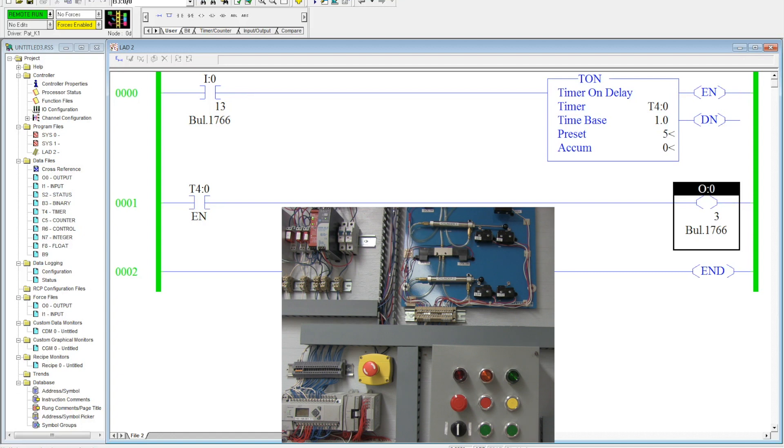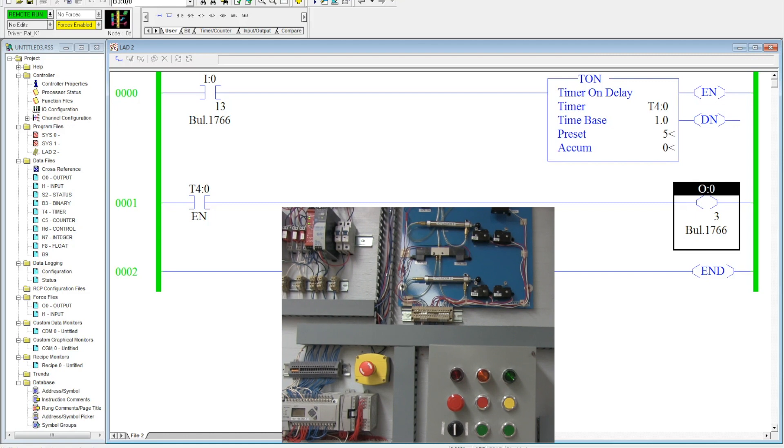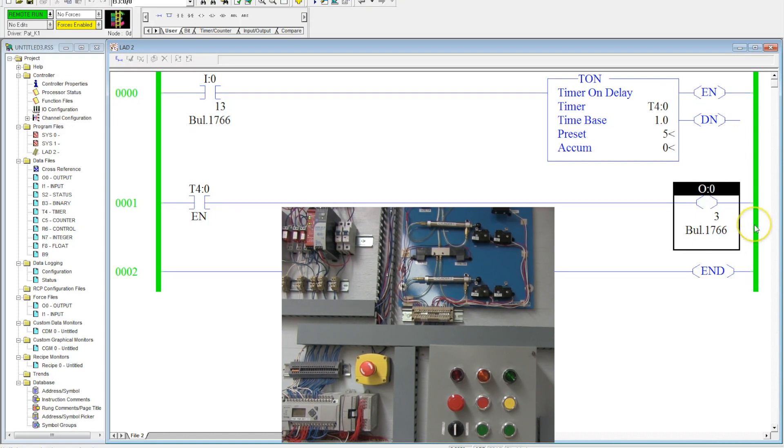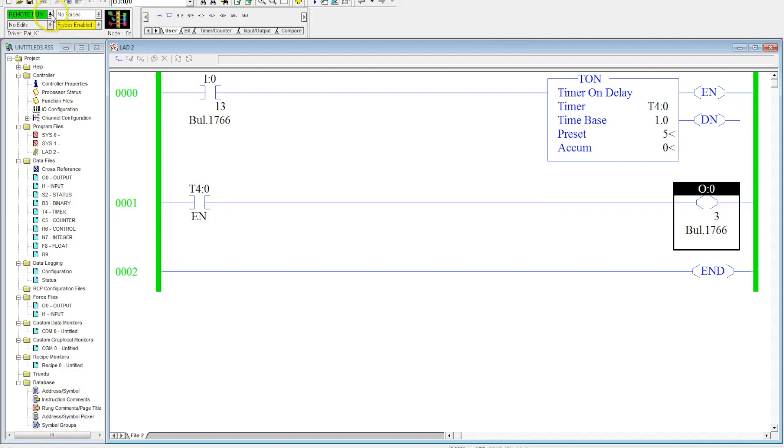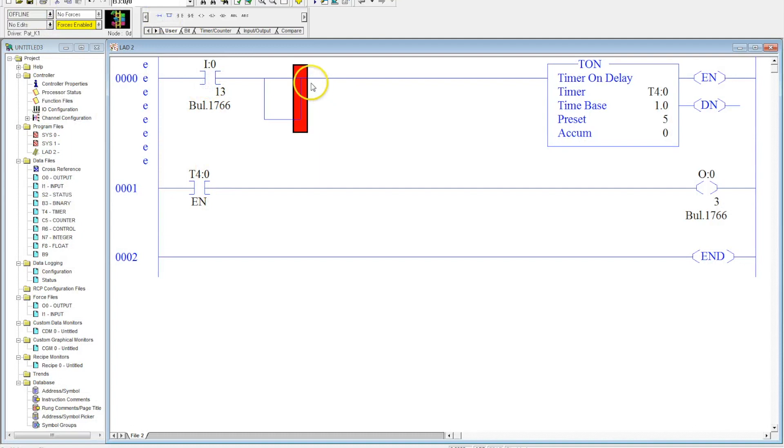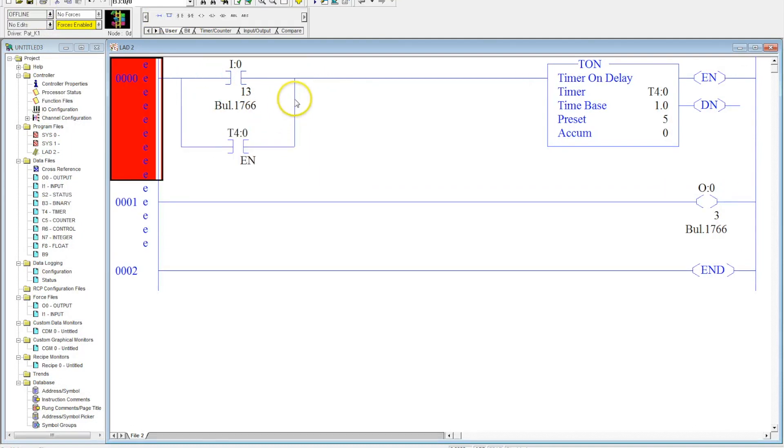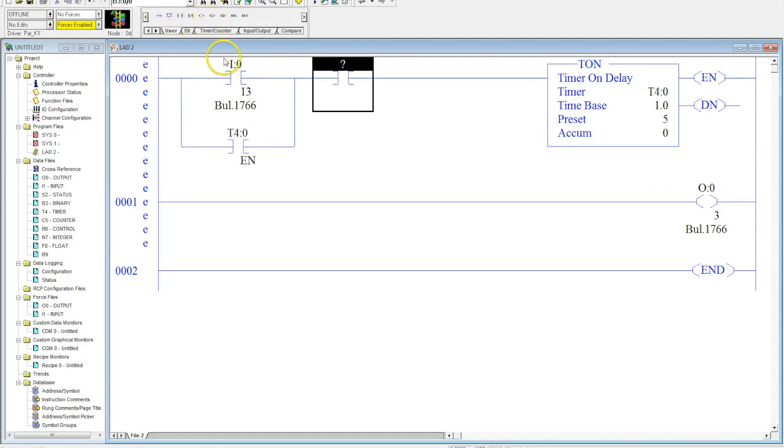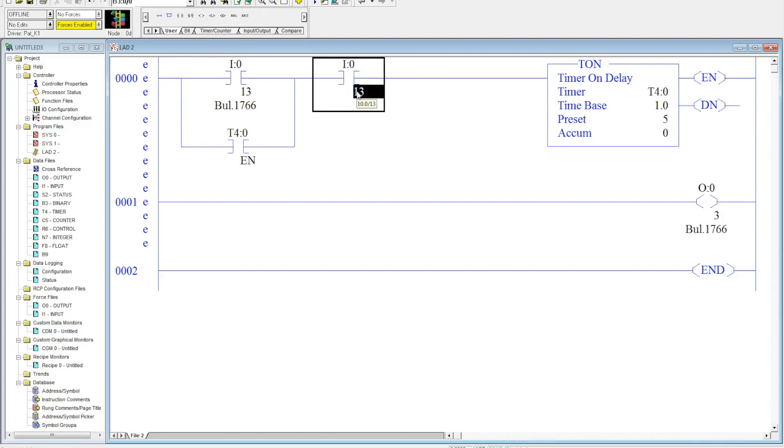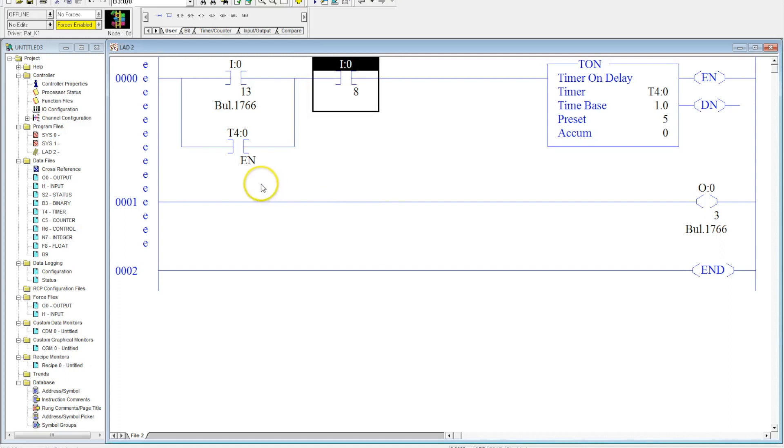Now the enable bit is typically associated with a memory contact for the timer. Let me show you what that means. I'm going to go offline, I'm going to put memory around here. I'm going to move this enable bit up here and then I'm going to throw a stop button in here. We will now use this enable bit as memory for this. This avoids you needing to put a B3 in there to latch that timer in for memory.